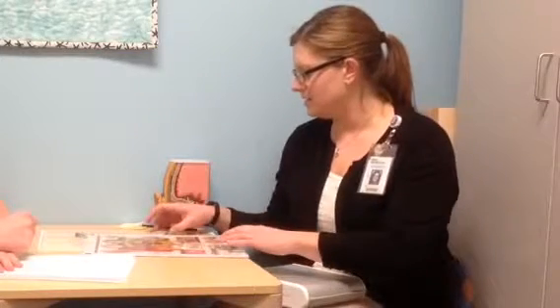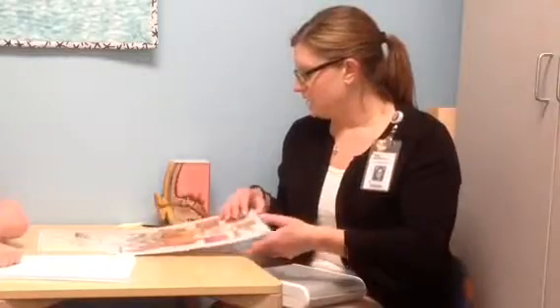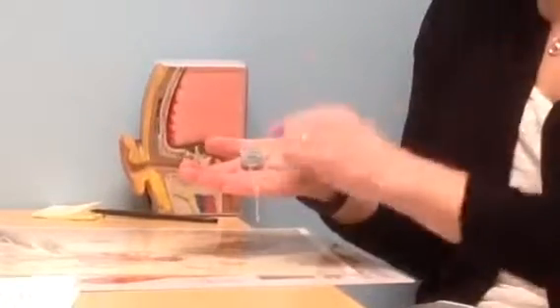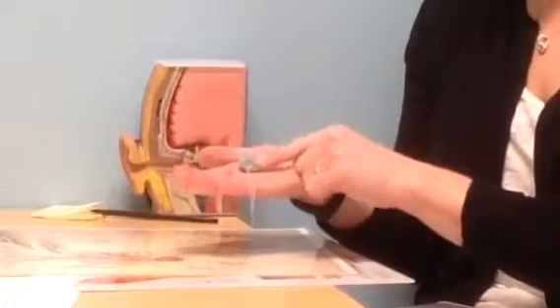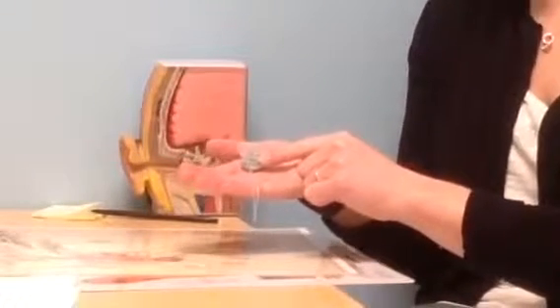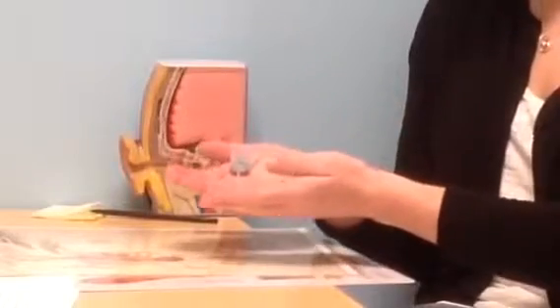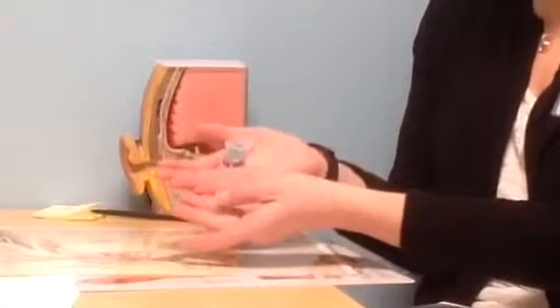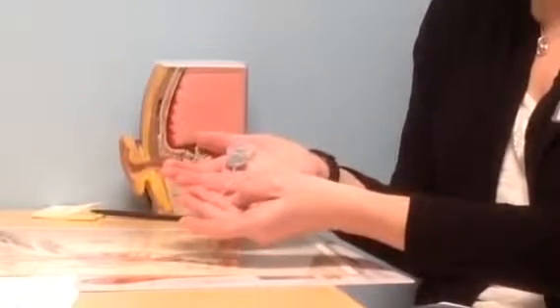So a cochlear implant is designed to provide electrical stimulation to a damaged cochlea, so a deafened cochlea. And so it consists of 2 main components. There's an internal component, which this is an actual example of one. And the internal component has the magnet that keeps the speech processor on. Kind of a plate. This is the area we call the receiver stimulator. This is the brains of the operation. That's the processing chip, and also what tells the implant how to do its job. And then down here at the end is our electrode array that actually goes into the cochlea.